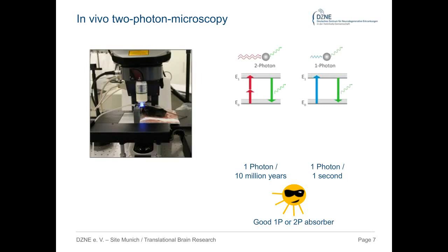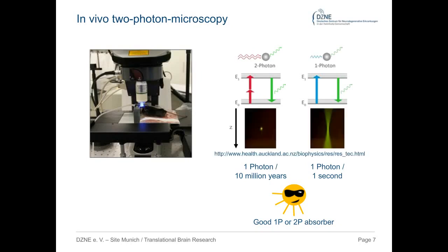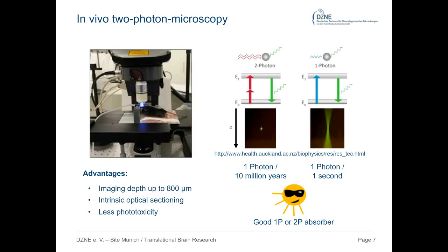Using a pulsed laser with high peak power and a focused beam, we obtain measurable fluorescent excitation restricted to the focal spot, with intrinsic optical sectioning in the z-direction — in contrast to one-photon excitation where the whole light cone is excited. Two fluorescent-filled cuvettes illustrate this: single-photon excitation shows the whole laser beam visible, while two-photon excitation restricts fluorescence to a single focal spot. Main advantages over conventional laser scanning microscopy include penetration depth over 800 micrometers into brain tissue, intrinsic optical sectioning, and reduced phototoxicity.